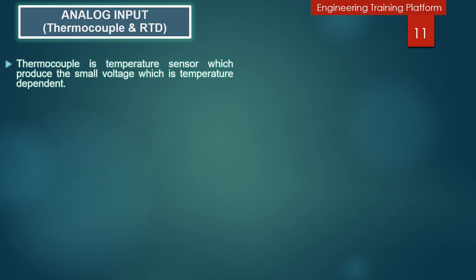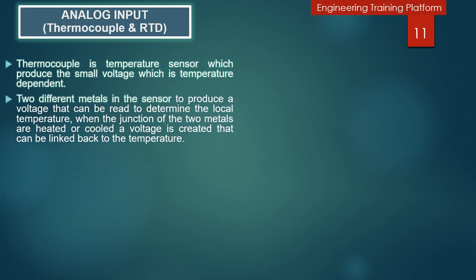A thermocouple is a temperature sensor which produces a small voltage that is temperature dependent. It consists of two different types of metals joined together at one end. When the junction of the two metals is heated or cooled, a voltage is created that can be linked back to the temperature. A thermocouple is a simple, robust, and cost-effective temperature sensor used in a wide range of temperature measurement processes. Thermocouples are manufactured in a variety of styles such as thermocouple probes, thermocouple probes with connectors, transition joint thermocouple probes, infrared thermocouples, bare wire thermocouples, or even just thermocouple wire.